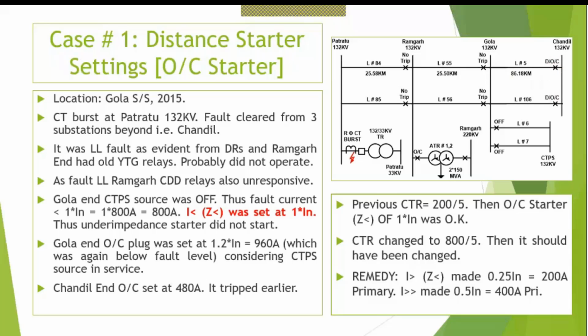Okay. So when we change CT ratios, if there are overcurrent and starters, the starter reaches also have to be changed. Otherwise, the fault may not start at all. Okay, that was a lesson learned from this particular case. There was one more lesson learned.